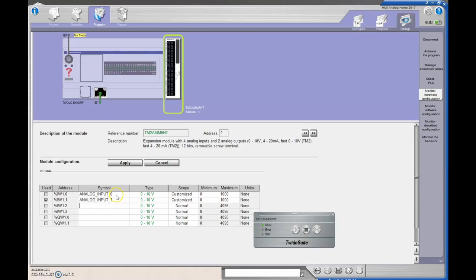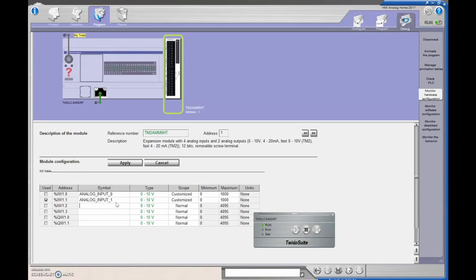So I was trying 0, I thought there was a fault on my input 0, so I tried number 1, it ended up that I forgot to provide my analog card with 24 volts DC, but I'll walk you through that and I'll show you how I screwed it up.